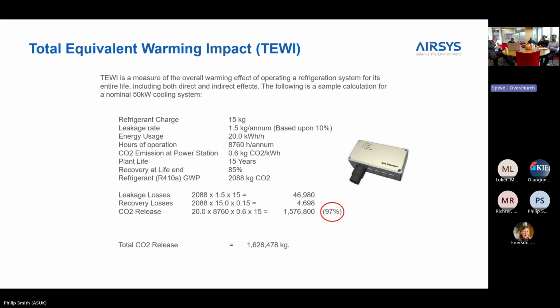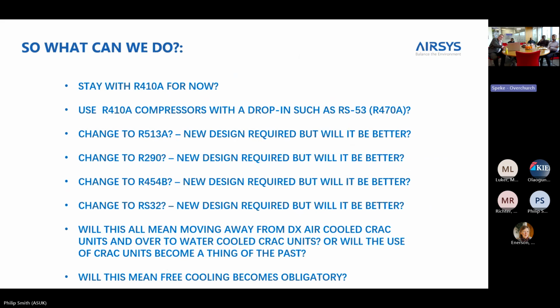However, the fact of the matter is that legislation is driving us as a business to look at removing refrigerants, full stop. So the fact that they don't account for that much isn't being considered as much as perhaps it should be, but it's just a valid point to be made. So what can we do? Well, most manufacturers at the moment are treading water and staying with the 410A that we have done for many years until a better product comes along.